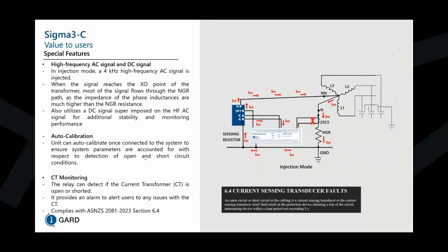In addition to that, there is an auto calibration feature which is going to be rolled out that allows the unit to auto calibrate once connected to the system, to ensure system parameters are accounted for with respect to detection of open and short circuit conditions. And we're also performing CT monitoring, so the relay can detect if the current transformer is open or shorted, and it provides an alarm to alert users to any issues with the CT.